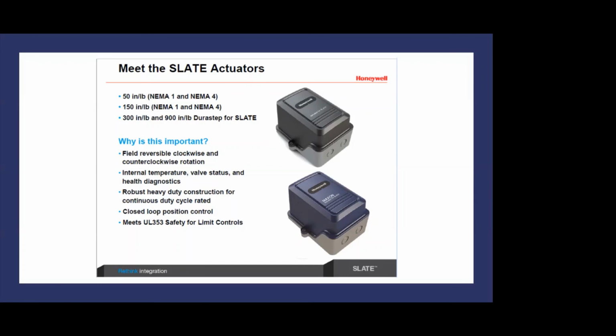If you get into that industrial space, that's where we see these, right? The systems are larger. You're moving more air. You need a more robust actuator. So the point here is, we have actuators that can cover an array of applications in the market. They are field reversible, clockwise and counterclockwise. And here again, look at the diagnostic features that we get out of these actuators: temp, valve status, health diagnostics, obviously COM, deviation, all of that information, very beneficial when we're wanting to stay on ratio and provide that efficient combustion to our customers.